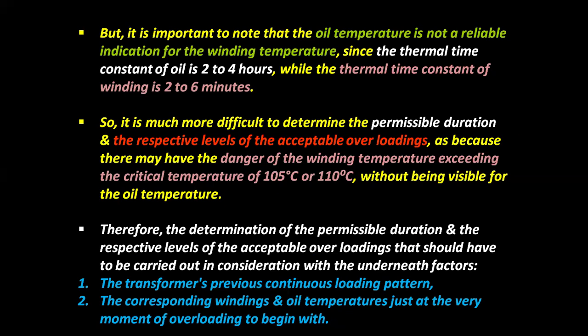Therefore, the determination of the permissible duration and the respective levels of acceptable overloading should be carried out in consideration of the following factors. Number 1: the transformer's previous continuous loading pattern. Number 2: the corresponding winding and oil temperatures at the very moment the overloading begins, that is, at the point of starting to overload the transformer.